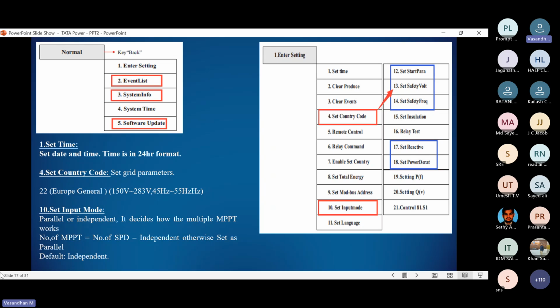The tenth option is set input mode, which has two conditions: parallel and independent. For example, if the customer is connected with PV strings — even multiple strings — we use independent mode. If the customer is using a Y connector, we use parallel mode. These two modes are very important.